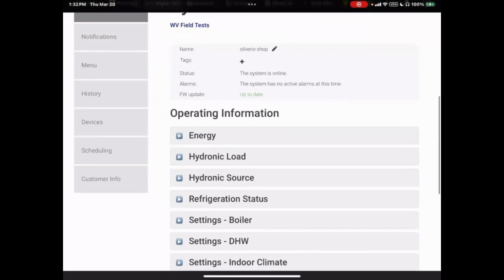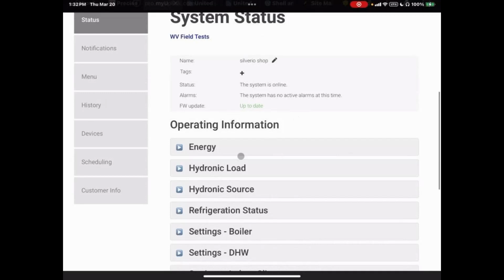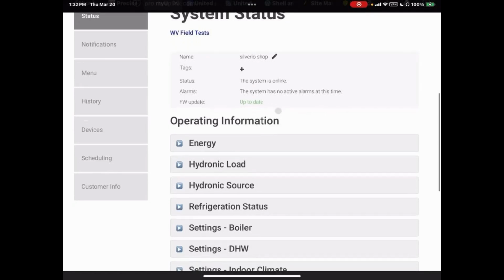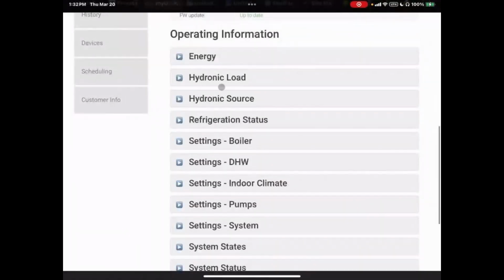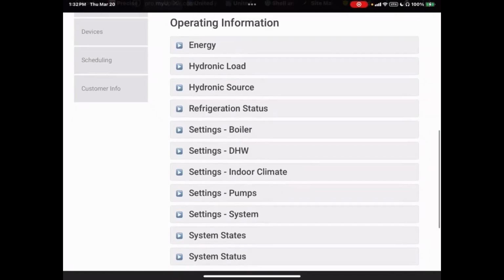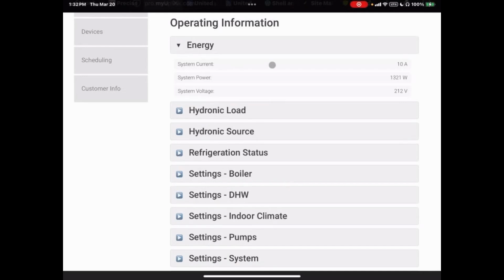As I scroll down here, I can see that we have the system name. It says that yes, we are online and there are no active alarms at this moment, and the firmware is up to date. Moving down from that, we have operating information. This operating information is just a snapshot in time, and I can drop down any one of these categories. Like this one right here, energy, we can see currently the system current is 10 amps, the system power is 1321 watts, and the voltage is 212 volts.